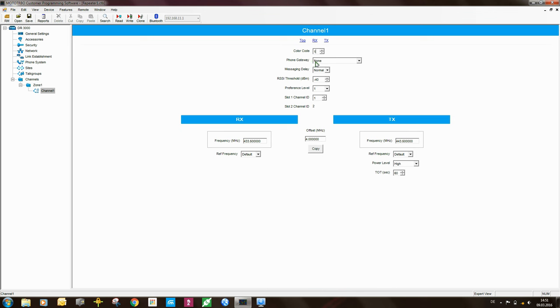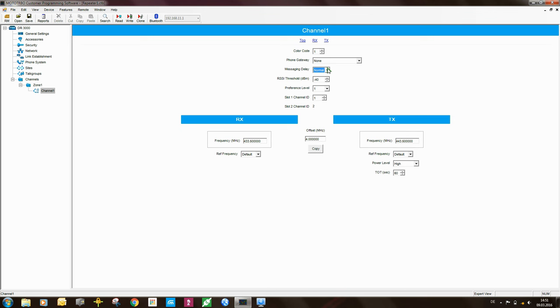Telephone gateway, I'm not worried about. Messaging delay, so this is basically the size of the buffer. So if you have a network connection between the sites which has a slightly higher latency, you'd probably want to change the messaging delay. But if you leave it at normal, it should be good for most cases.